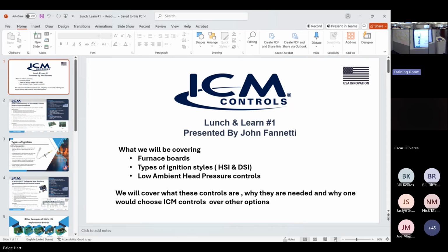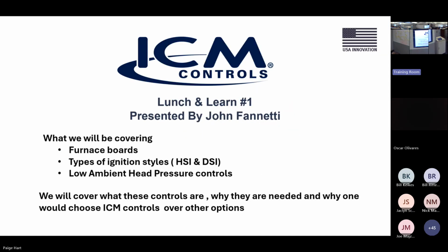We're going to talk a little bit today about furnace boards. That is a fall preseason topic, it's part of the fall preseason. Also, we're going to talk about types of ignition styles. The furnace boards can come in two different major styles: hot surface ignition and direct spark ignition, different ways we light the fire for a furnace or a boiler. And then we're going to talk about another very important control for this type of climate, which is the low ambient head pressure controls. We're going to cover what these controls are, what they do, why they're needed, and why somebody would choose ICM controls compared to some other brands out there.